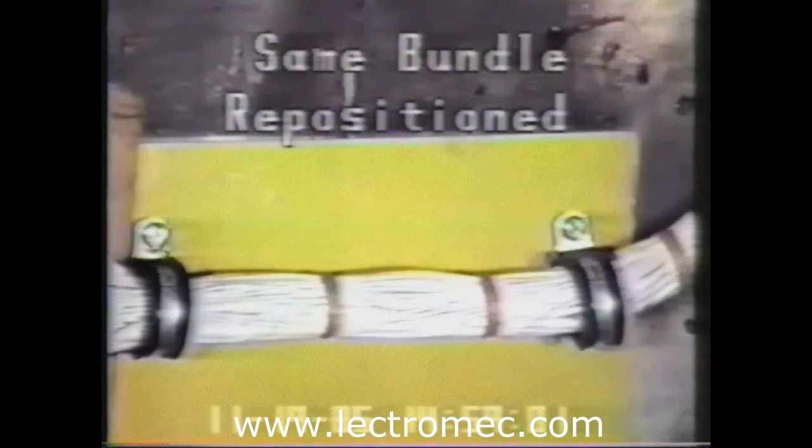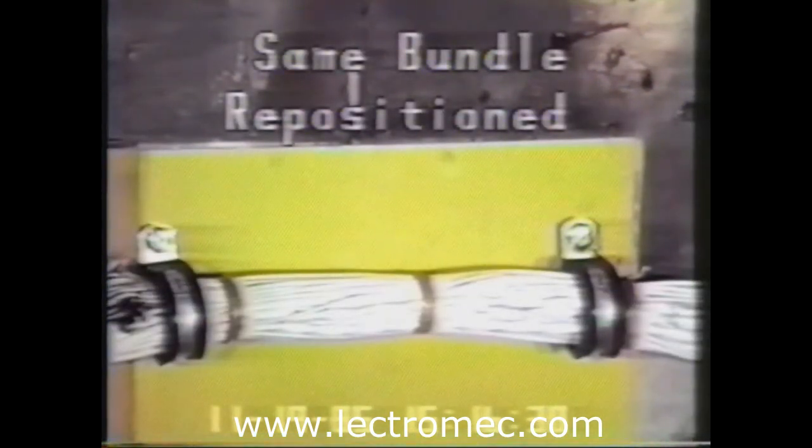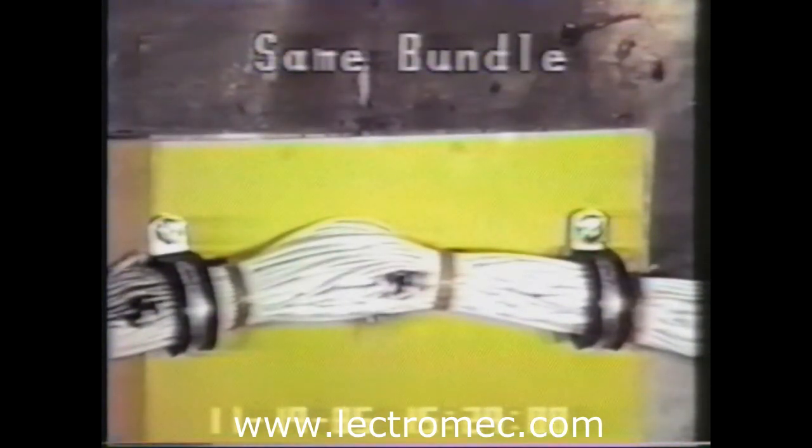The same harnesses were also assembled using MIL-W-22759/34 type wires in order to provide a comparison between the two types of insulation. Since the first shot did not trip any circuit breakers, the same harness was reused by moving an undisturbed section into the line of fire. As was observed on some of these shots, there was immediate arcing, but none of the intense burning and arc propagation seen in tests of the MIL-W-81381 type wire.